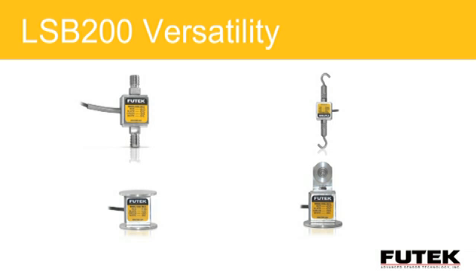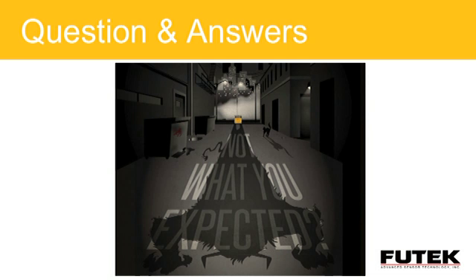On your upper right, some hook assemblies are used a lot in bag weighing, or you have some type of tray that you're hanging off the load cell, because it will give you a direct inline loading. On the bottom right, it's similar to what was shown in that fiber tension example. You have a bearing inside of a pulley system, giving you the capability to get a compression or tension force due to some type of fiber, small rope, or anything you can run through that pulley system.